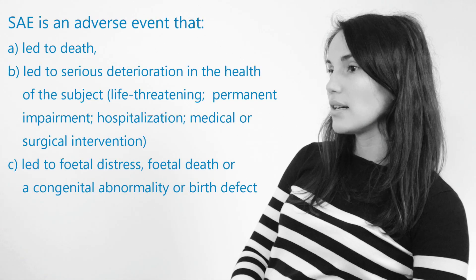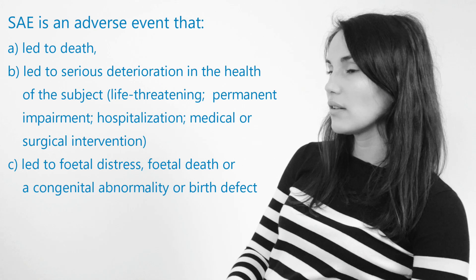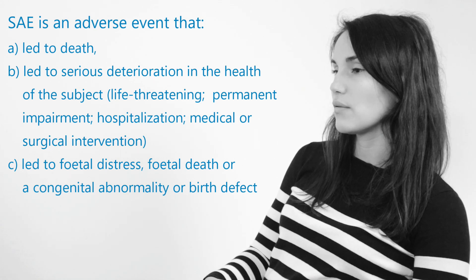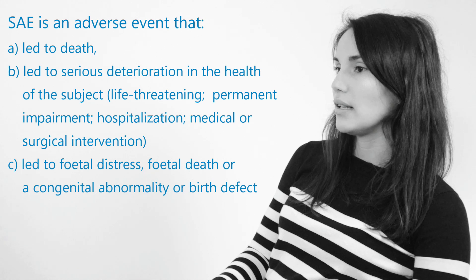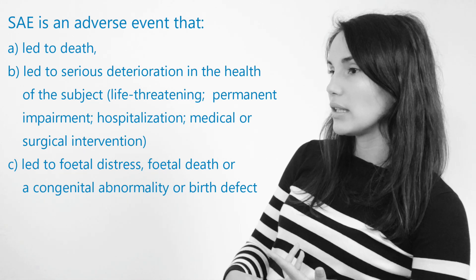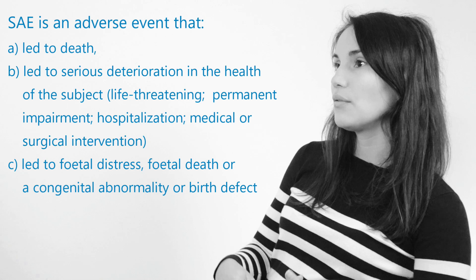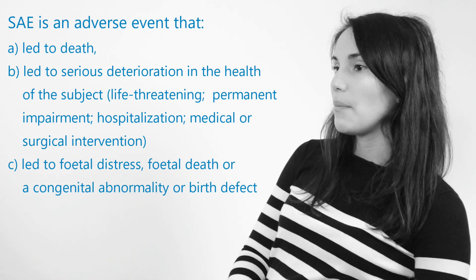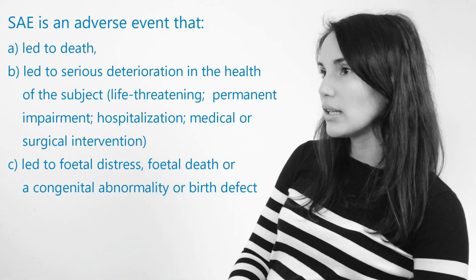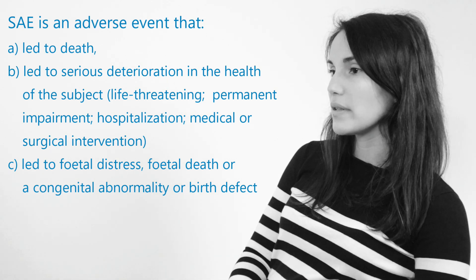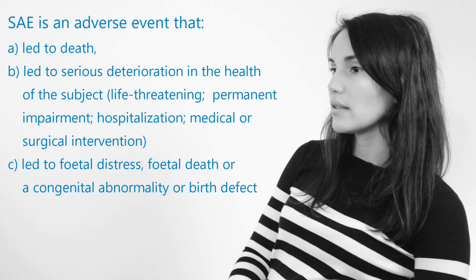An adverse event is not a side effect, but what makes an adverse event serious? The adverse event becomes serious only in the following cases: if it led to death, if it led to serious deterioration in health such as a life-threatening illness or injury, a permanent impairment of body structure, hospitalization or prolongation of hospitalization, medical or surgical intervention to prevent a life-threatening event, or fetal distress or fetal death.